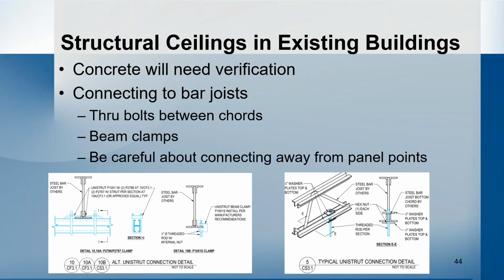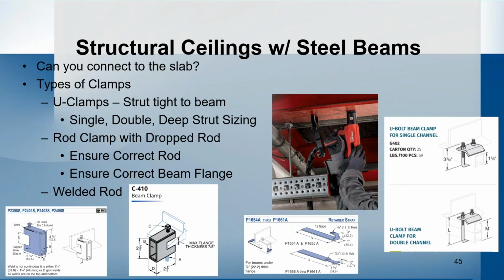On some projects we've done recently, to avoid the coordination, the contractor just ran a continuous strut beneath, parallel with the bar joist, and then hung from the strut. So they were able to keep their connections close to the panel points and drop directly from that strut wherever they needed to.